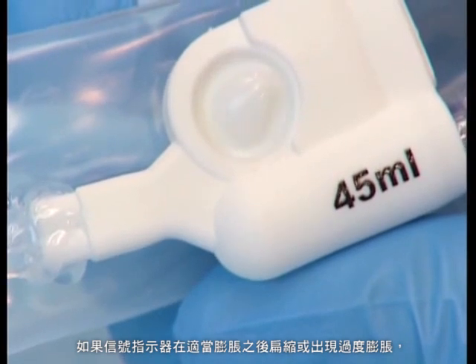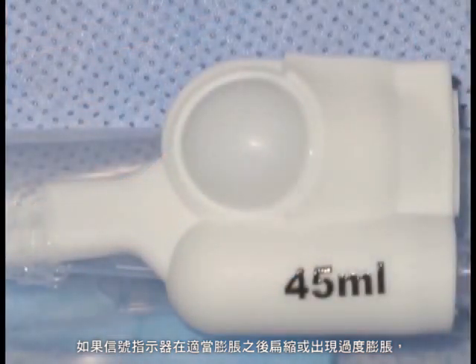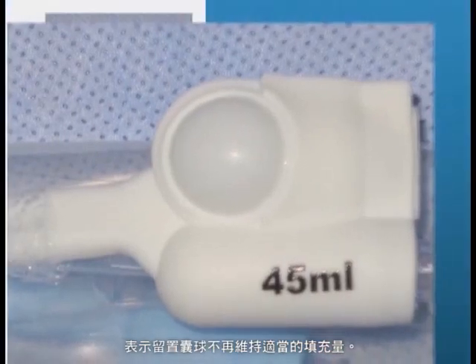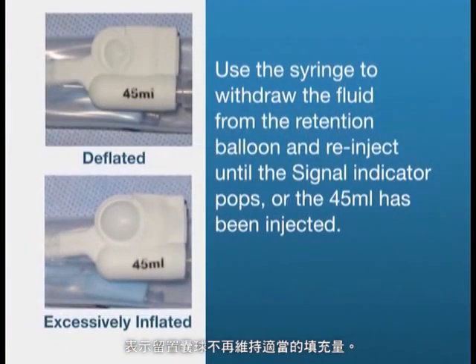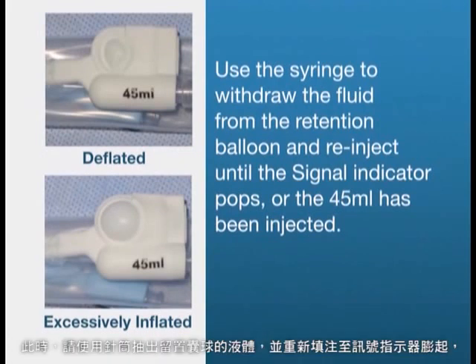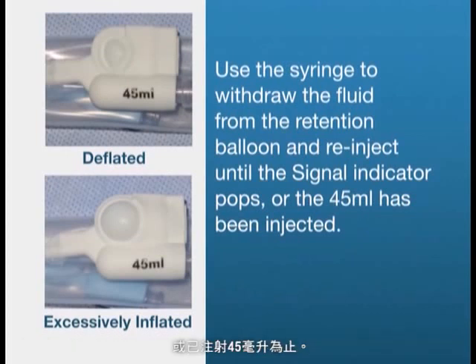Should the signal indicator deflate or appear excessively inflated after proper inflation, this is an indication that the retention balloon is no longer at the optimal fill level. In this case, use the syringe to withdraw the fluid from the retention balloon and re-inject until the signal indicator pops or 45 ml has been injected.